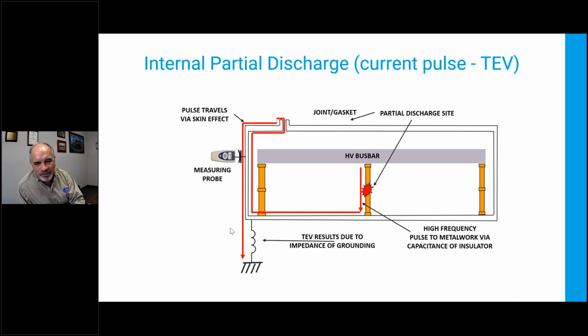It can't go through the cabinet. At these frequencies, it won't go through a cabinet, won't go through copper, won't go through even foil shield on a cable. It has to travel on the surface of the metal. So what happens is it travels all around the inside of the cabinet trying to find a path to ground, right? It's a current, it wants to go to ground. And what it does is it eventually finds a gasket or a joint or a door or something, gets to the outside of the cabinet, looking all over for a place to go.